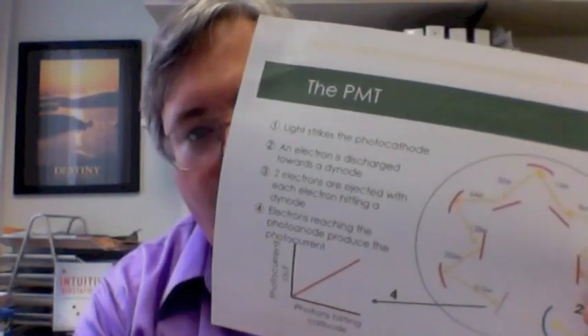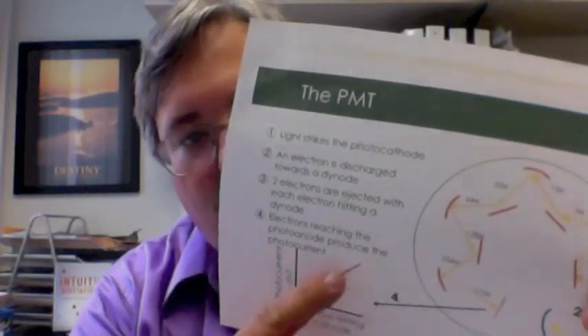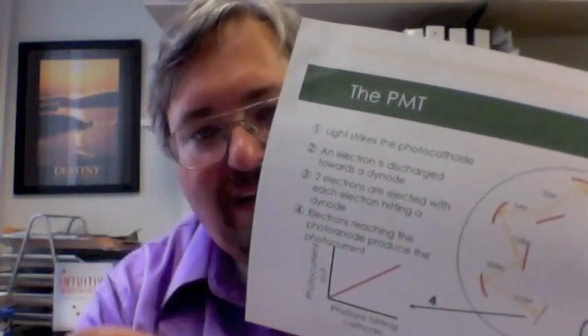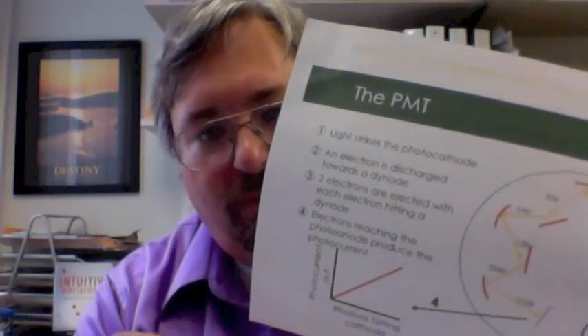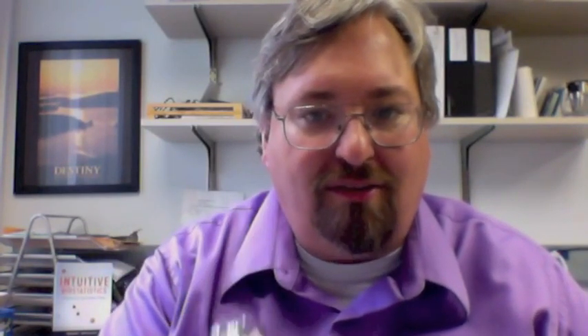What's really cool is at this end here, this is where the photocurrent comes out. Critically speaking, the photocurrent is directly proportional to the intensity of the photons striking that photomultiplier tube. This PMT is what's working in your system to convert photons of light to current, and that's exactly what a photomultiplier tube does. And that's what a flow cytometer is — it's nothing more than a photocounting device, and it relies on this right here.